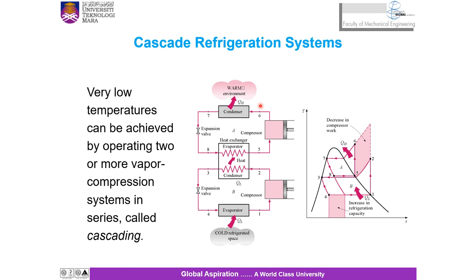So one way of dealing with such a situation is to perform the refrigeration process in stages - one stage followed by another stage. This means having two or more refrigeration cycles operating in series, as shown in the diagram. This type of refrigeration cycle we call cascade refrigeration cycle. What we have here is a two stage cascade refrigeration cycle.